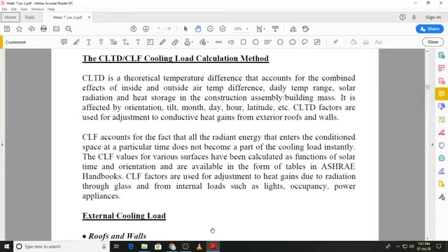And that thermal radiation that is entering the conditioned space does not become part of the cooling load immediately, because the air is transparent to thermal radiation. So that thermal radiation that enters the conditioned space does not heat up the air instantly. First it is absorbed inside and raises the temperature of the surfaces, then that heat that is absorbed is convected away by the air. So there is a sort of time lag, and to account for that factor we need the cooling load factor. And again, the cooling load factor will be found from tables that we have for occupancy, for example, and for lights.